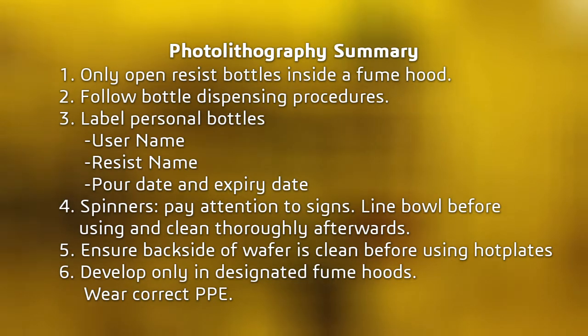For spinners, pay attention to posted signs regarding allowed resist and solvents. Line the spinner bowl before use, and always clean your spinner afterwards. Ensure the backside of your wafer is clean before using the hot plates.